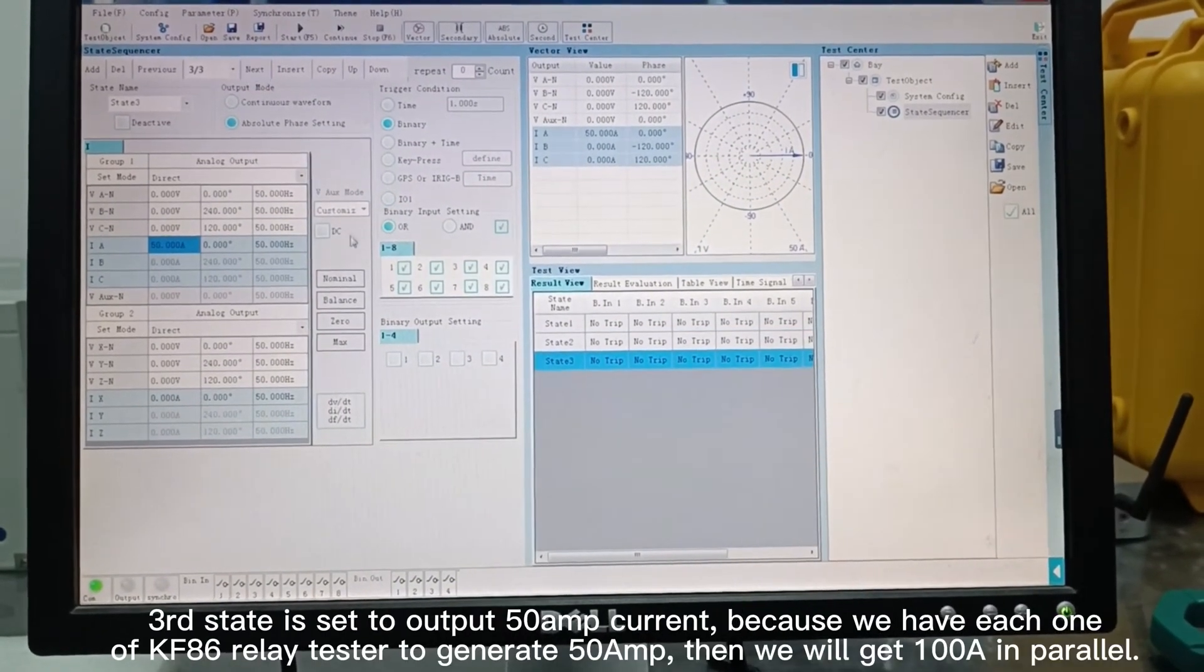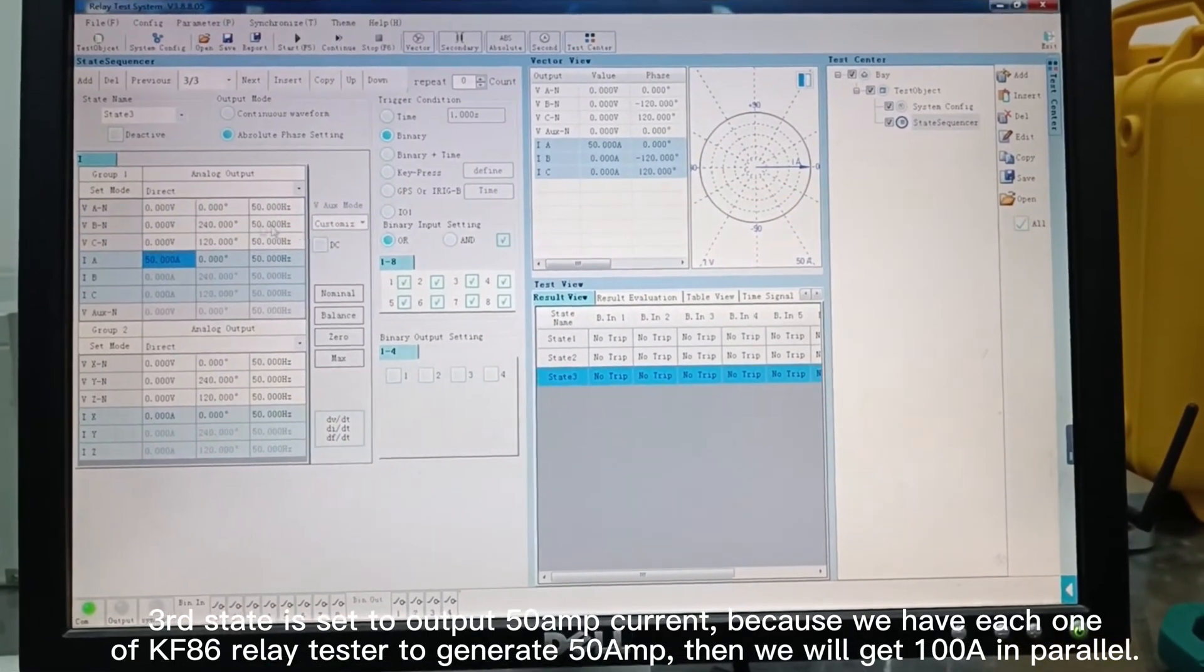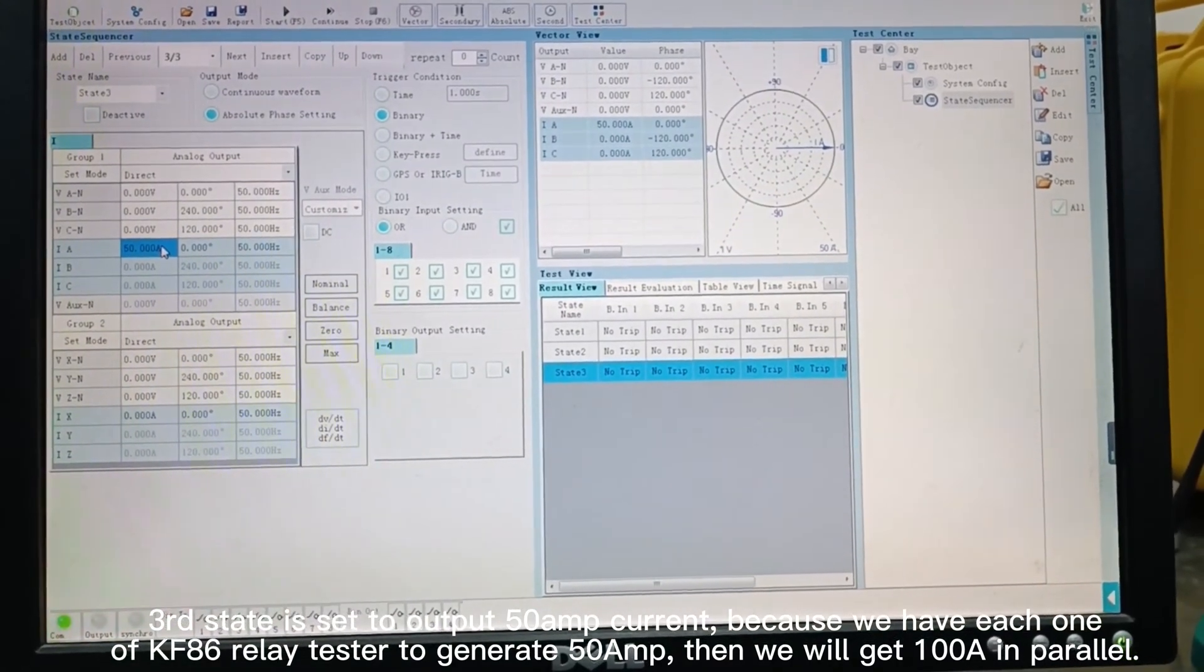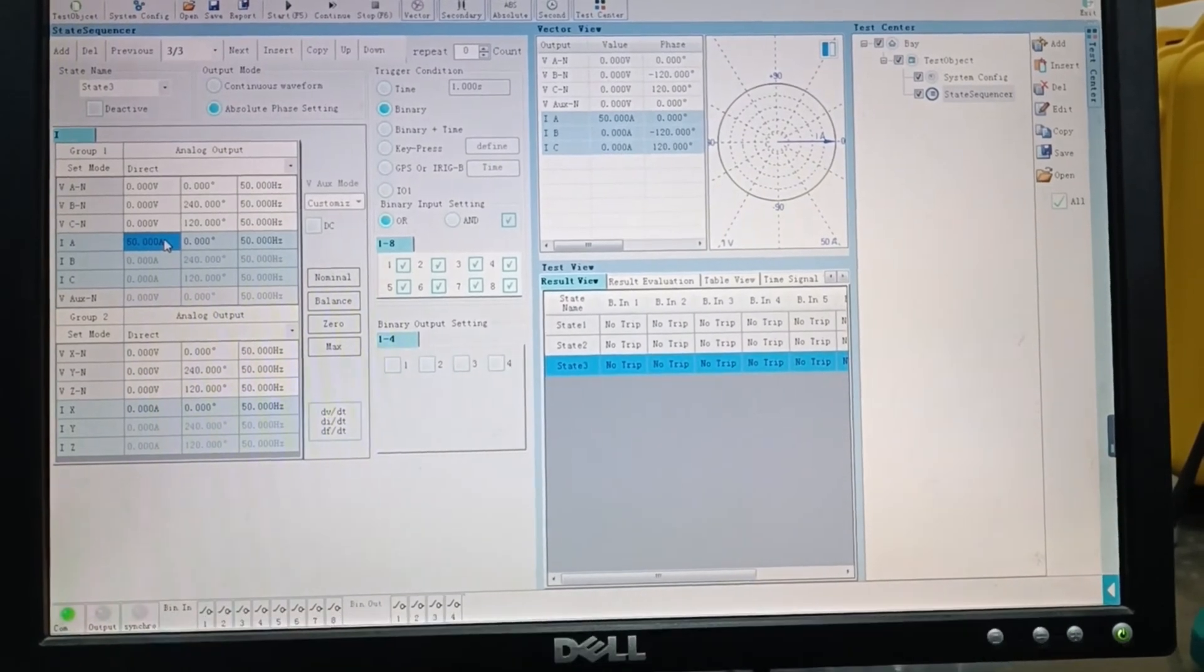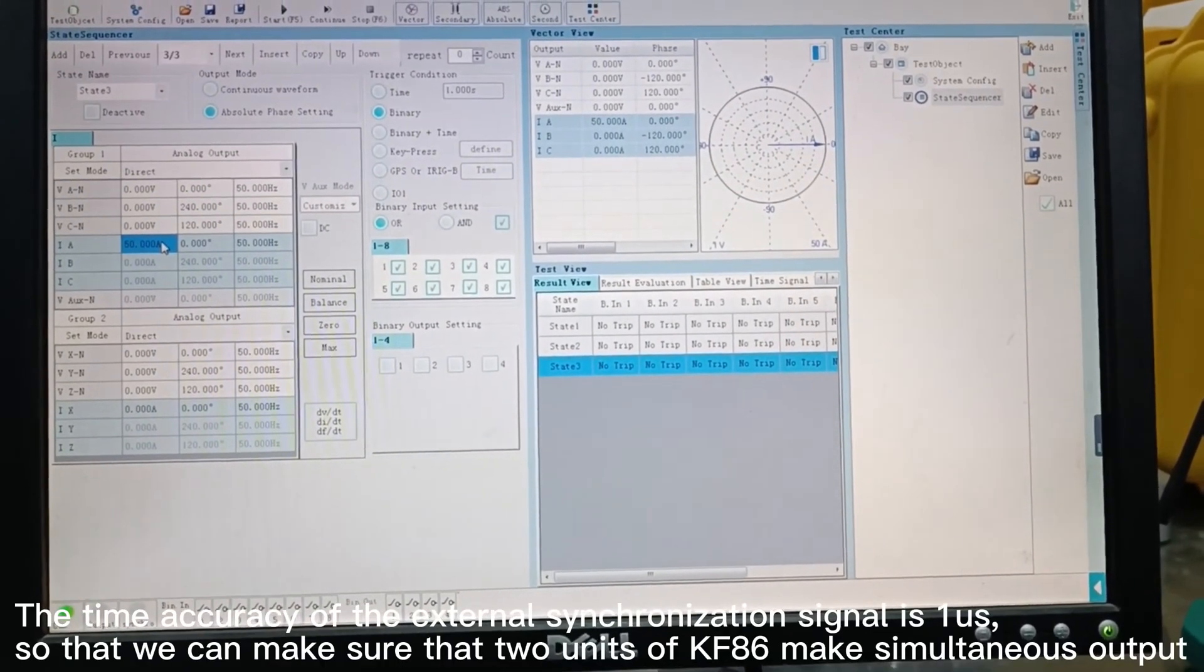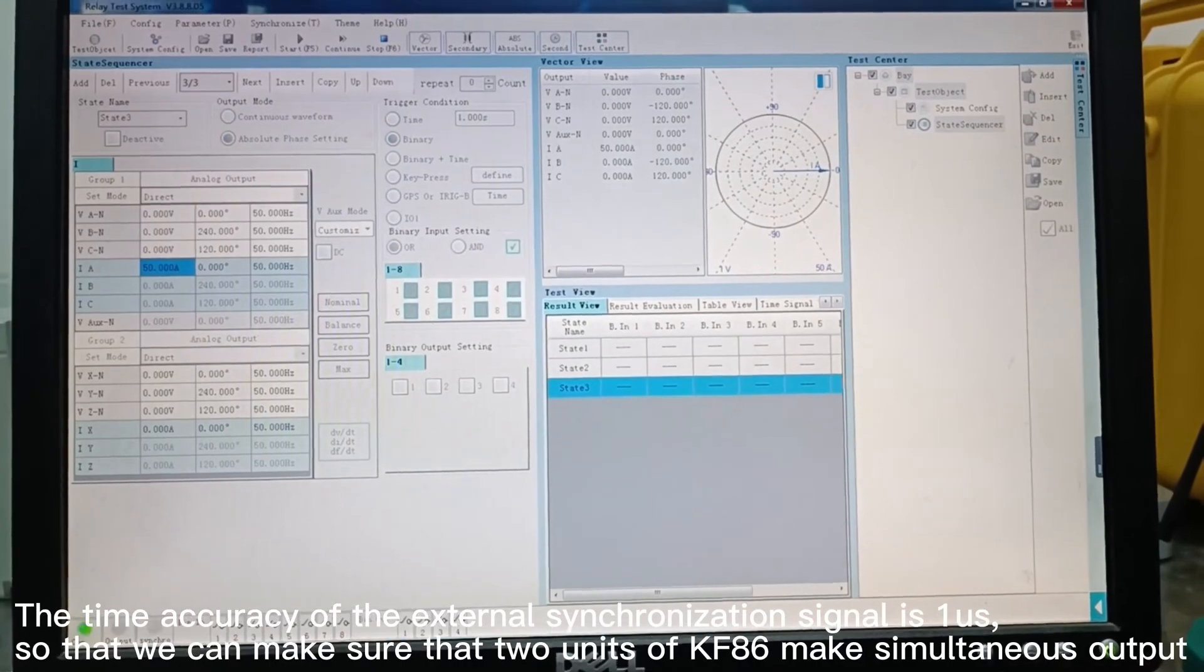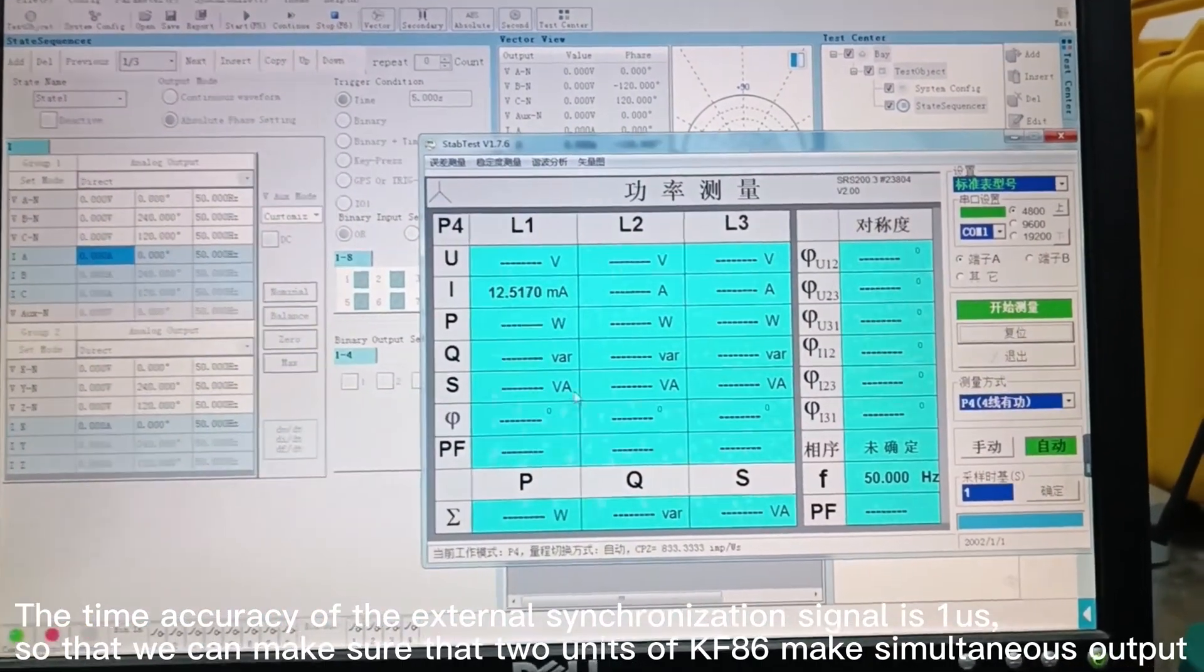Third state is set to output 50A current. Each KF86 relay tester generates 50A, then we will get 100A in parallel. The time accuracy of external synchronization signal is 1 microsecond, so we can ensure that the two units of KF86 make simultaneous output.